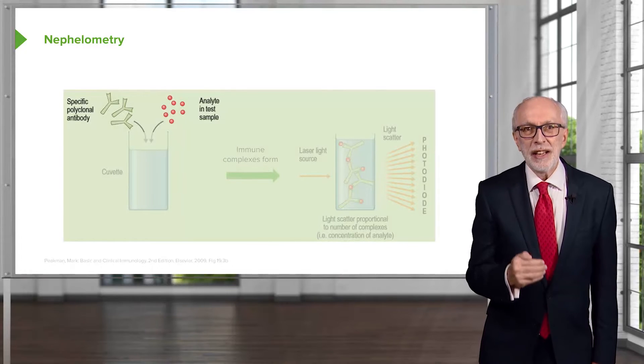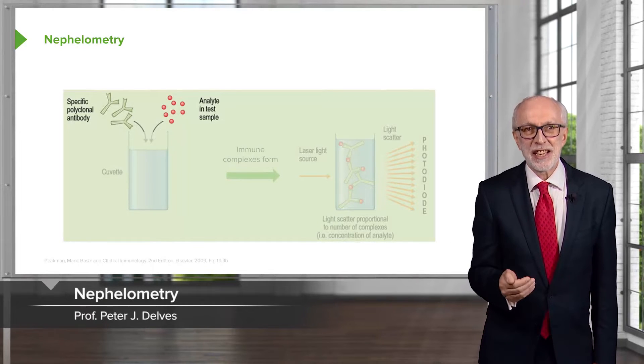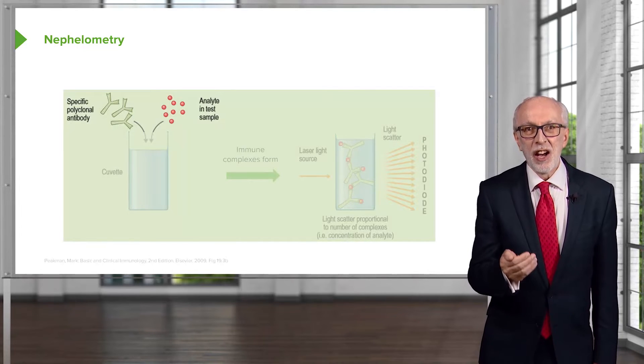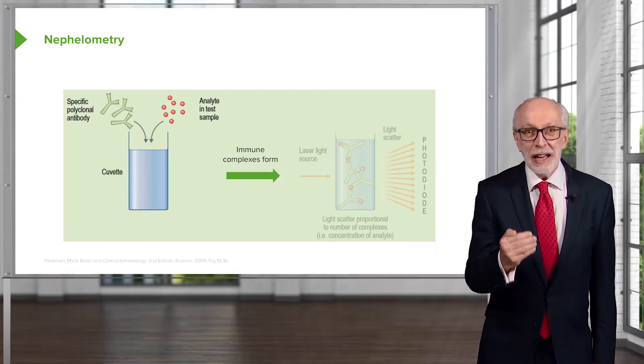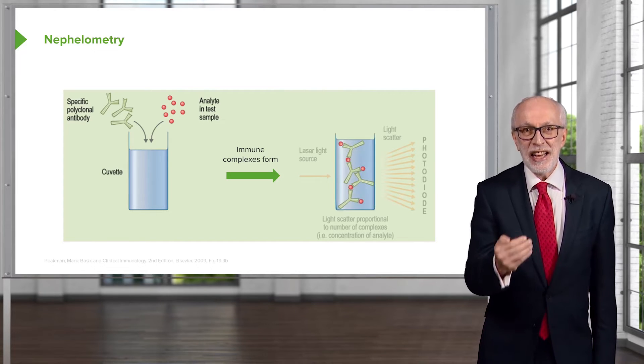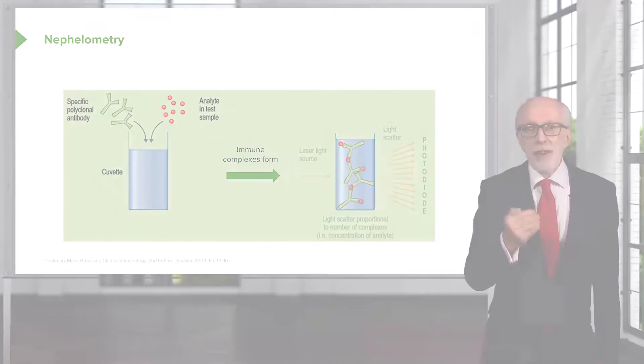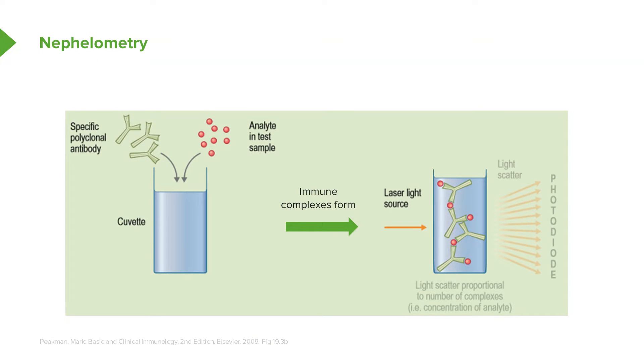In nephelometry, the presence of an analyte in a test sample can be detected. Specific polyclonal antibodies are mixed with the sample containing the suspected analyte. These are added to a cuvette and immune complexes will form if there is the analyte for that particular antibody present in the test sample. Laser light is then shone onto the cuvette and there will be light scatter depending upon the amount of immunoprecipitate that is formed. The light scatter is detected using a photodiode and is proportional to the concentration of the analyte.